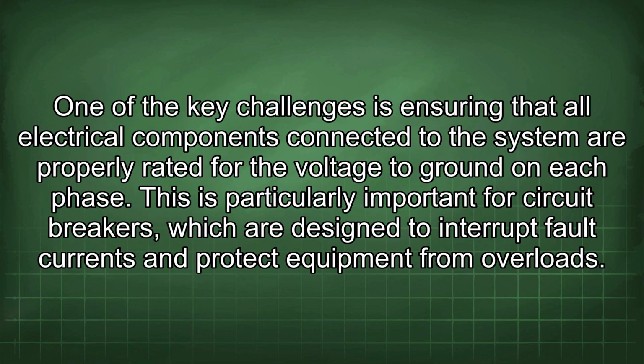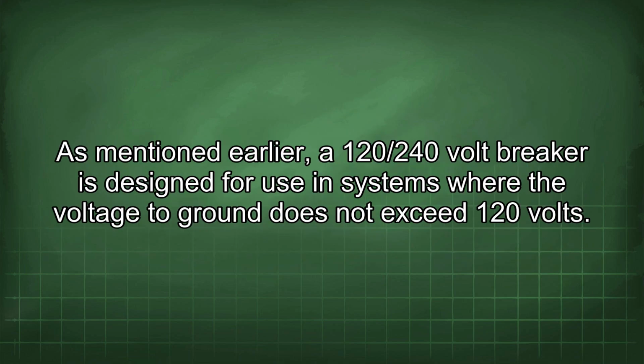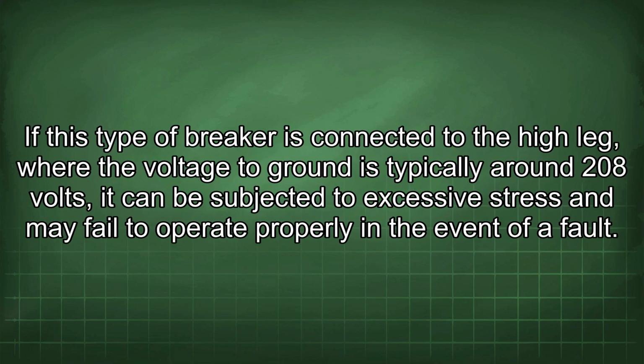One of the key challenges is ensuring that all electrical components connected to the system are properly rated for the voltage to ground on each phase. This is particularly important for circuit breakers, which are designed to interrupt fault currents and protect equipment from overloads. As mentioned earlier, a 120/240 volt breaker is designed for use in systems where the voltage to ground does not exceed 120 volts. If this type of breaker is connected to the high leg, where the voltage to ground is typically around 208 volts, it can be subjected to excessive stress and may fail to operate properly in the event of a fault.